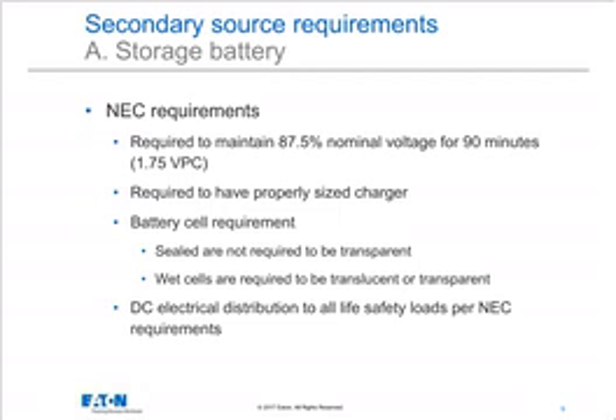The battery cells themselves, the actual container that the battery is in, if it's a sealed battery, then those cells can be made of opaque plastic or Lexan or whatever acid-resistant material is intended. If it's a flooded electrolyte battery, meaning the kind of battery where we have to add water on a regular basis, those batteries need to have either a translucent or a transparent case so that I can see the level of liquid inside and know when I need to add water. Much more common to see sealed batteries rather than the wet cell type for this application. But in an extremely large building, you might see wet cells.